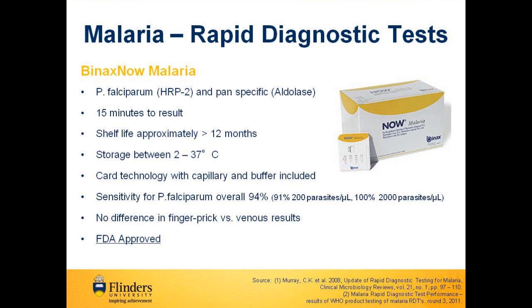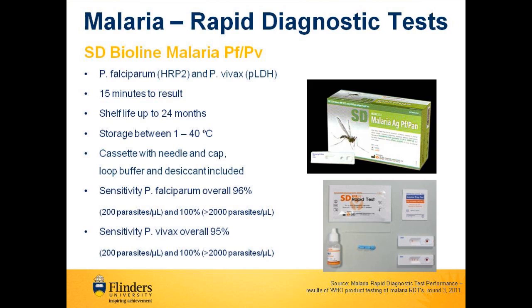The SD Bioline malaria RDT is a cassette technology that can differentiate between Plasmodium falciparum and Plasmodium vivax. It has a long shelf life of up to 24 months and a storage temperature of between 1 and 40 degrees Celsius. In Round 3 testing by the World Health Organisation, the SD Bioline kit sensitivity for both Plasmodium falciparum and Plasmodium vivax was 95% or greater for different parasite loads.